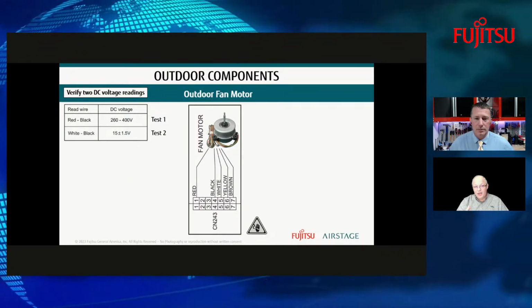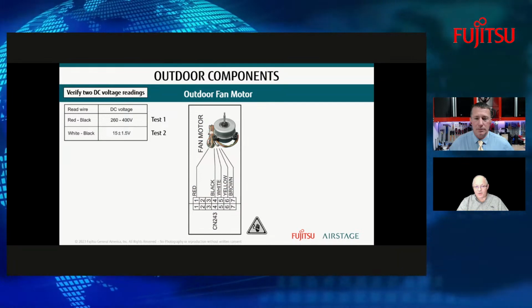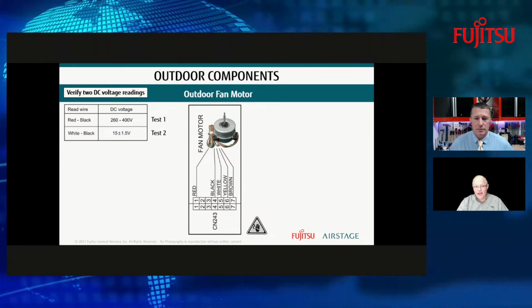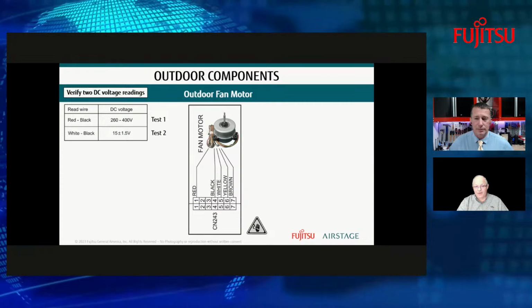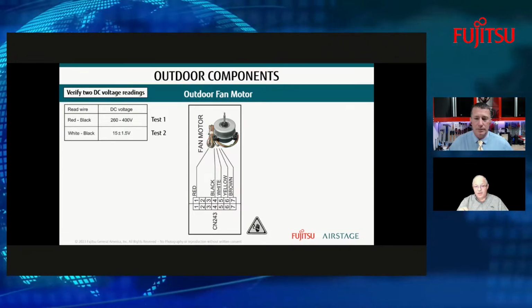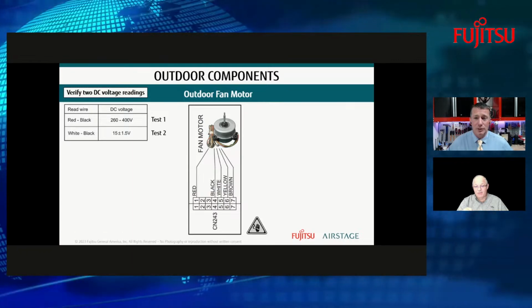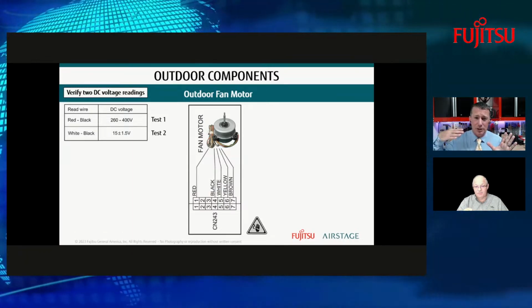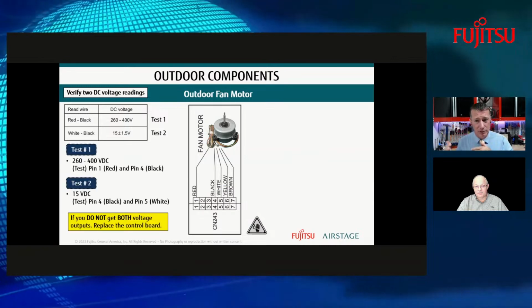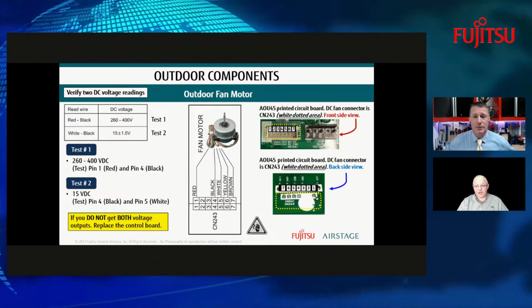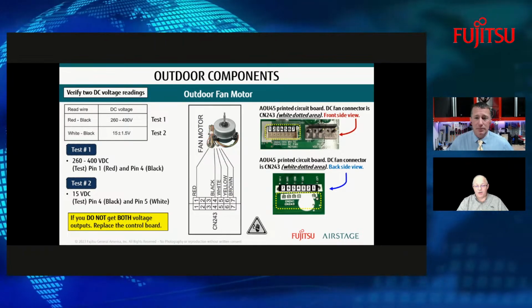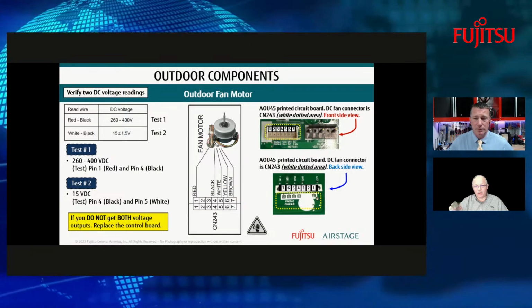But then if a technician went out, he would also have to check the white and the black wire, and he'd have to have something between 13.5 to 16.5 volts. If he got both of those voltages, then that motor should be running. So we're basically looking at incoming line voltage on our high voltage DC and then our control voltage on our low volt DC? That's correct. So that can be checked by actually taking a reading on the board outside.